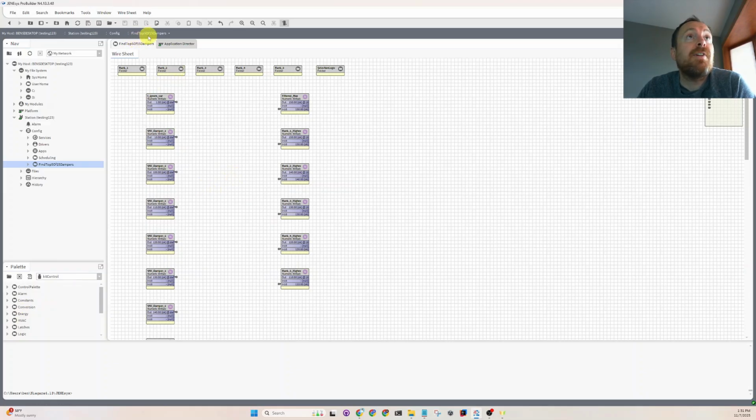So this is the top 5 of 15. They're labeled as VAV box damper positions, and this is what you would use it for. If we're starting down the road of Guideline 36, we would potentially be looking at an air handling unit system. So every VAV box damper position in the system, we would be monitoring those damper positions in Guideline 36. If we're doing trim and respond on the air handling unit duct pressure set point, we would be filtering out some potentially rogue zones that would interfere with the algorithm's performance.